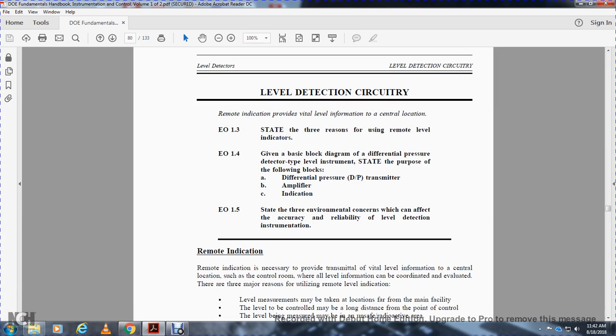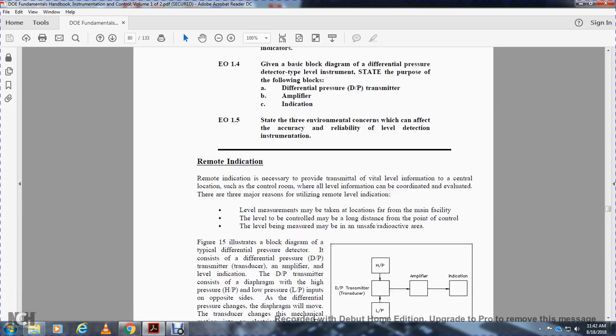Alright, level detection circuitry. Remote indication. For the remote indication, after they are provided with the transmitter, the vital level information is sent to the control room. There are three main reasons to utilize remote level indication. The level measurements may be taken in a location far from the main facility. The level may be controlled from a long distance, but the point where the level is being measured may be in an unsafe, radioactive area.